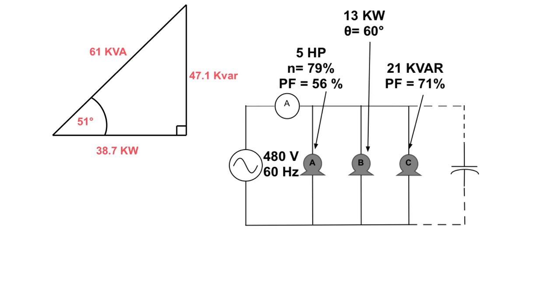Okay, let's move that triangle up there. Now, with 51 degrees, that doesn't help us out with our power factor. What we need to do is figure out what our power factor is. And just like I talked about over here, how power factor and angle are closely related, the same thing is true over here. You can just take the cos of 51 degrees is equal to 0.63. That's all you have to do. The cos of that angle gives you the power factor, 63% lagging. And there you go. Our next step is going to be to figure out what the current is. Our current is just going to be this kVA divided by this voltage. 61 kVA divided by 480 volts will give us our line current of 127 amps. There you have it. With no power factor correction capacitor in there, we are looking at 127 amps of current, source current flowing there.